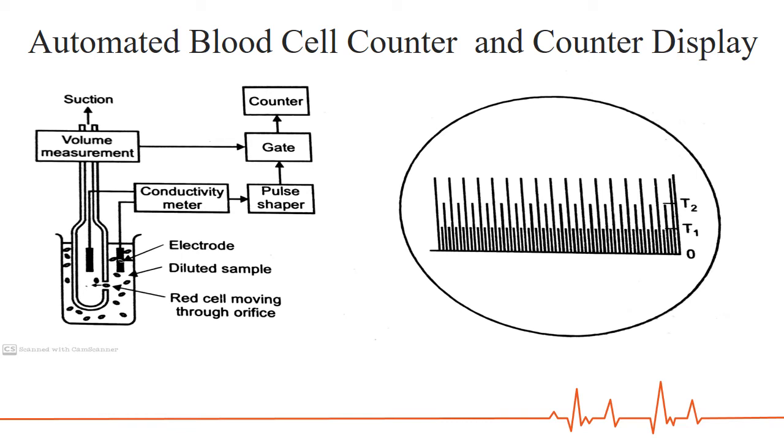During the operation of the instrument, the threshold is first set to 0 and the counter output is given by the total number of particles, WBCs and the RBCs together with the platelets per liter. Then the next step is to set the threshold to T1 and now the counter gives total number of RBCs and WBCs per liter. And last, the threshold is set to T2 and the counter just reads only the WBC count per liter.